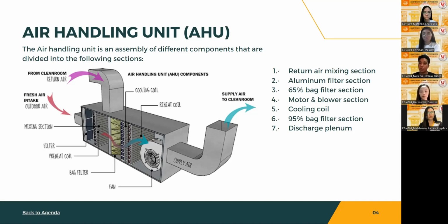This mixture of return and fresh air then passes through a series of 3 filters, which are the aluminum pre-filters, the 65% bag filters, and the 95% bag filters. After the initial filtration process, the air is pumped into the blower section, where a motor is connected to a centrifugal blower via a belt and pulley arrangement. After the blower section, the air is expanded by the diffuser plate so that it can travel uniformly through the cooling coil. The cooling coil cools and dehumidifies the incoming air so that the temperatures can be achieved. After the cooling coil, the air passes over 95% filters, which remove the fine particles suspended in air. Then finally, the air is pumped into the discharge plenum, which is connected to the central ducting system.